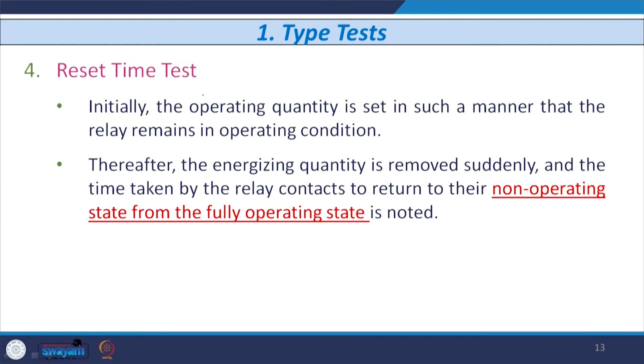So, this is all about the reset value test, and the next, related to the same, is the reset time test. Initially the operating quantity is set in such a manner that the relay always remains in operating condition, as I told you in the previous test, the reset value test. Thereafter the actuating or energizing quantity is removed suddenly, and the time taken by the relay contacts to return to their normal state from the fully operated state is noted, and that time is known as reset time. So, you have to take the next reading once the relay fully resets.